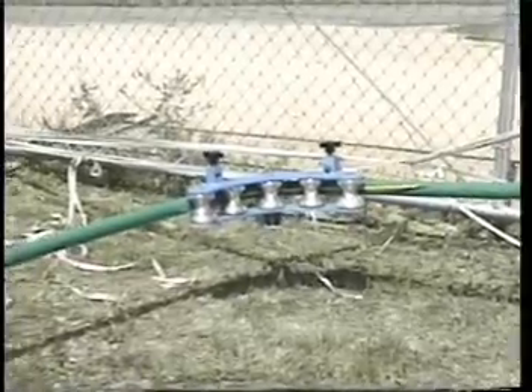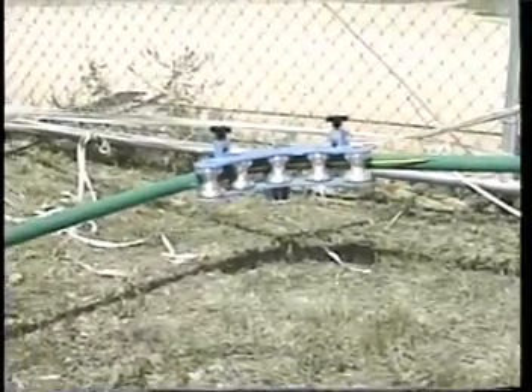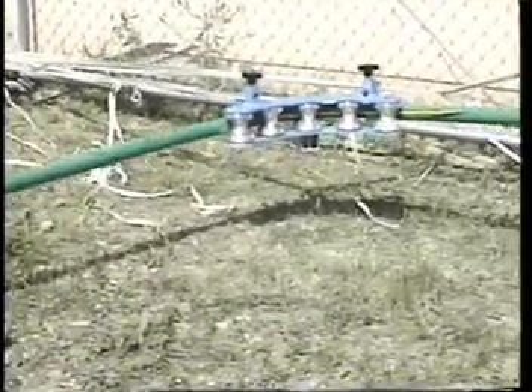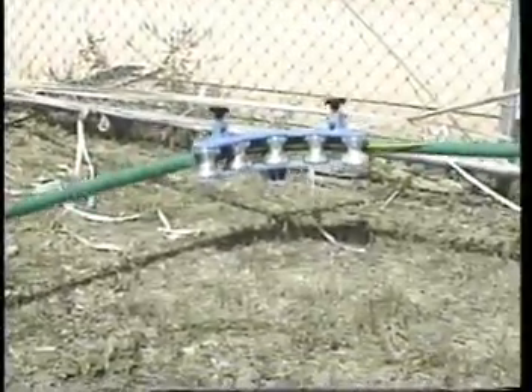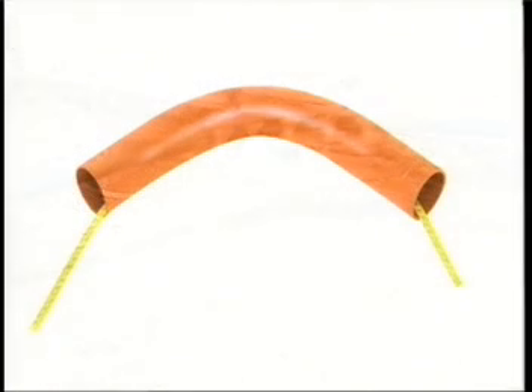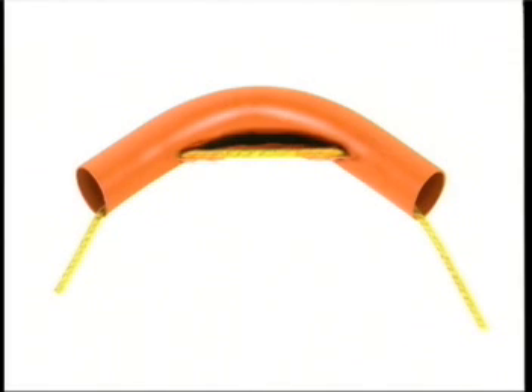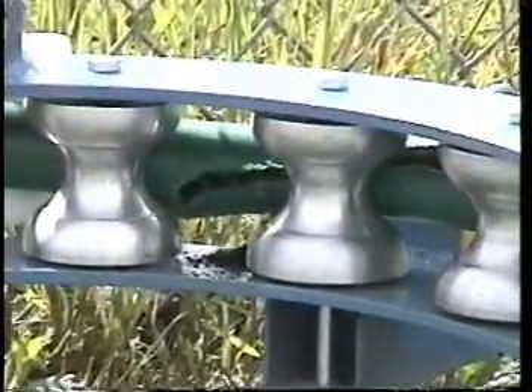As the rope surges, it actually saws through the plastic conduit. That's because the rope elongates as the cable resistance increases, and the resulting friction is concentrated at various contact points throughout the pull, due to the rope's round construction. Nowhere is this more apparent than at the sharp bends in the duct, where the surging rope burns through the conduit in seconds.